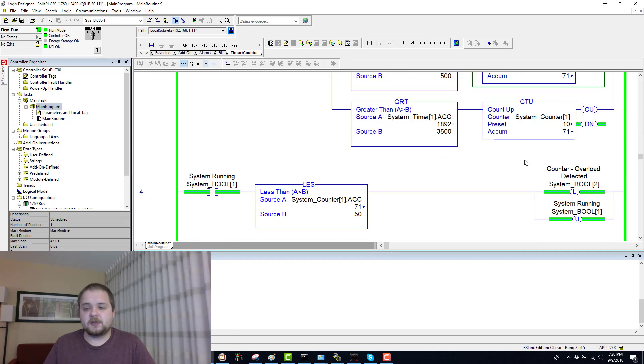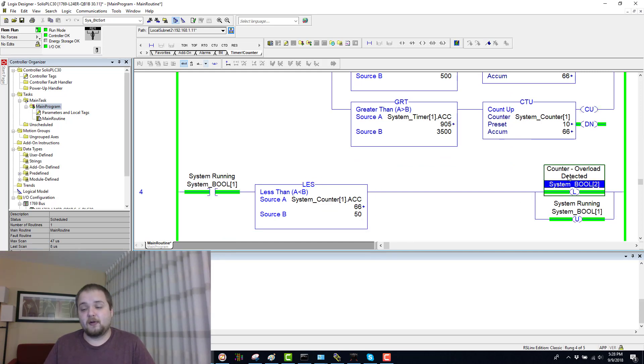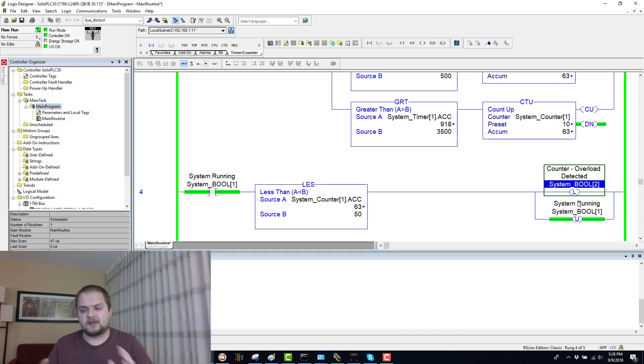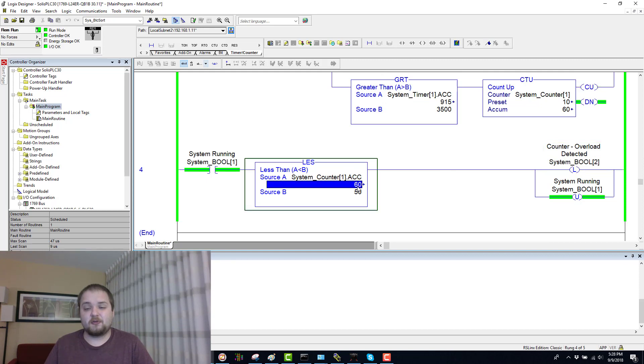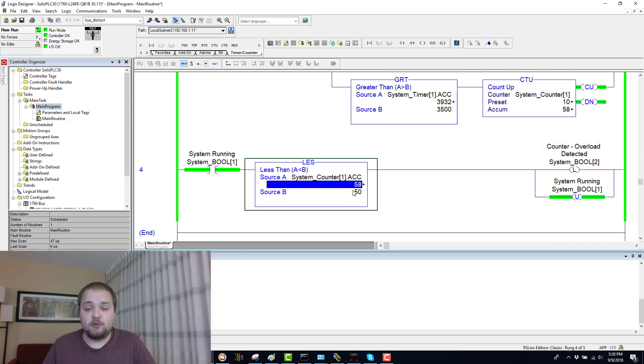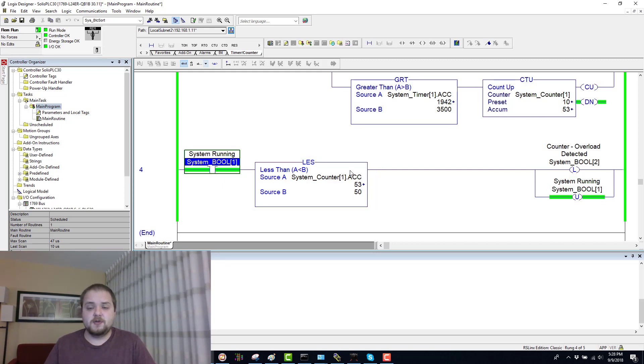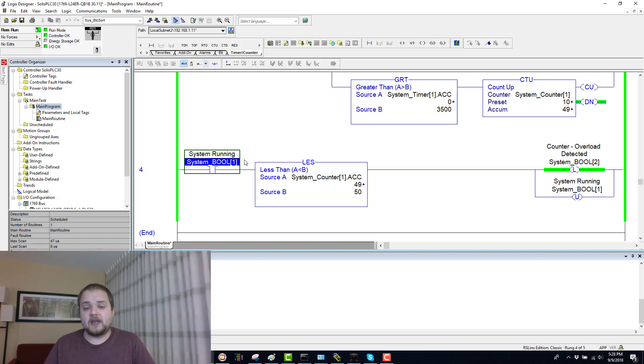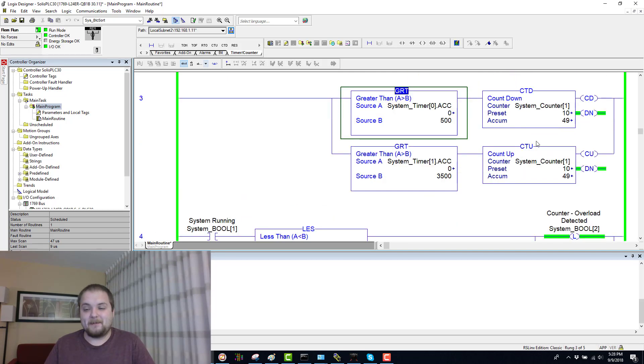If it reaches this 50, you will notice that since the system is running, as soon as it reaches less than 50, an overload or a conditional overload, and of course we can unlatch this, as soon as the system reaches a critical limit, and again you could have an upper and lower limit, the system will stop and it will prevent anybody else from starting your system due to that limit being reached. Very, very useful application, although I have not seen it done in many situations like this. It does apply to certain cases.